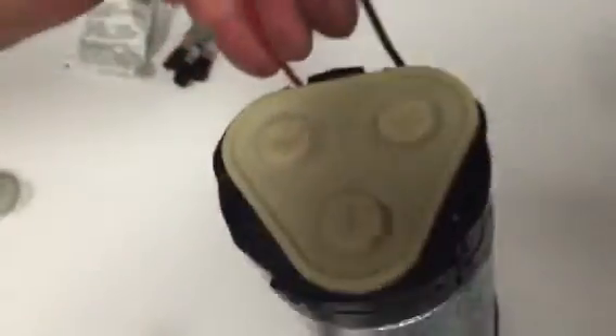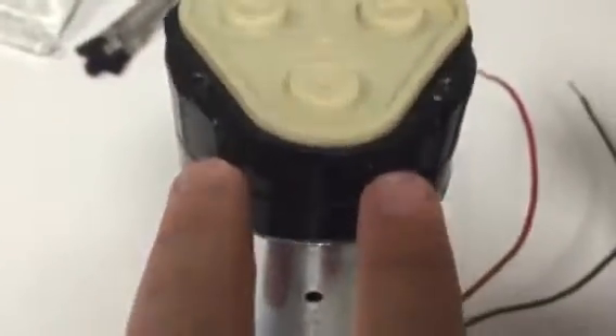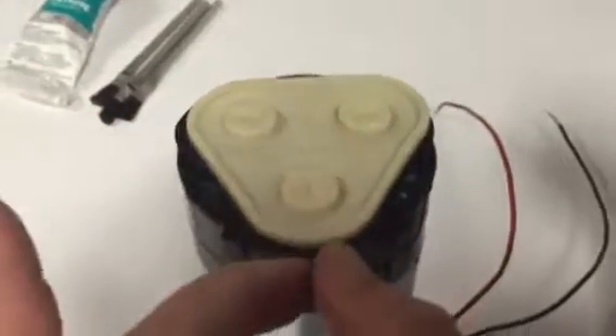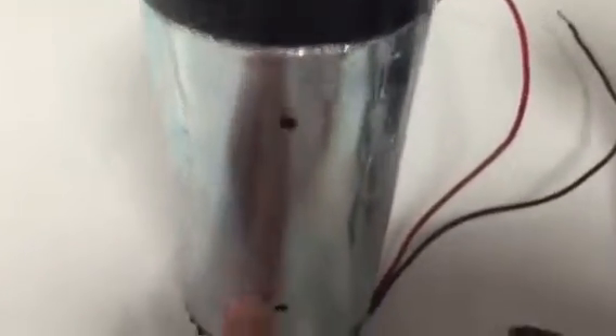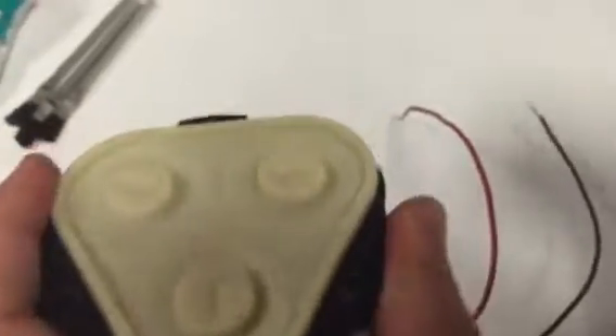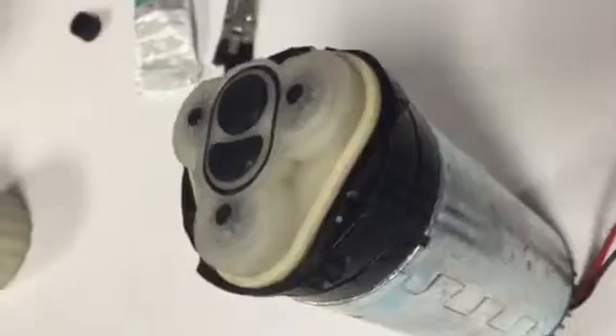So you can see the cables that come back out are going to come up and fit into these 2 slots that have been placed in the lower housing assembly. You can also line it up with these 2 notches here, with the point of the triangular part closest in, and it lines up with the holes on the shaft in the center here. So now you know you have proper alignment and proper seating of the lower housing assembly. Next we will take the valve housing assembly, and we're going to place that carefully on top of the diaphragm and seat it into place. So you push it in firmly.